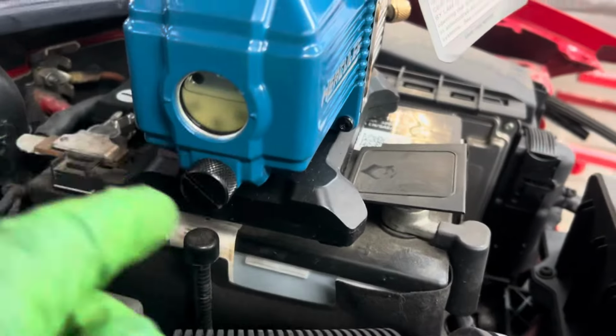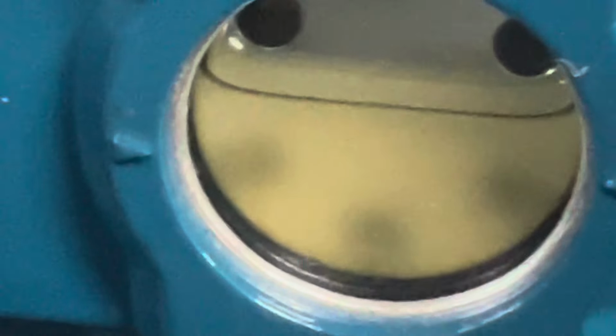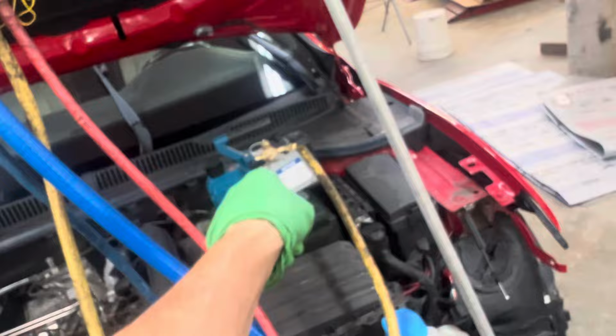But look at the oil. This is just pumping on this job. You see how cloudy that is? That was crystal clear when I started this job. Now this pump has to have the oil changed just after this one job. It was crystal clear, now it's dirty, now it needs to be changed. Check this out. This was crystal clear when I started. Now it's all hazy. And it's milky looking.